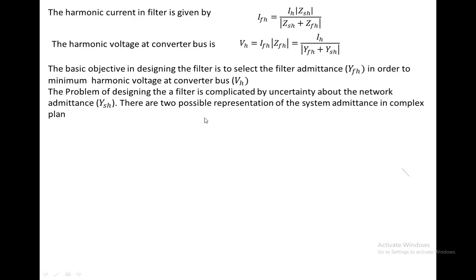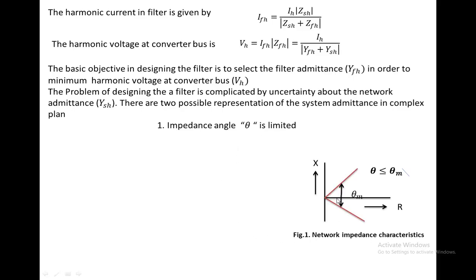There are two possible representations of system admittance in complex form. In the first method, the impedance angle theta is limited. On the x-axis we have resistance and on the y-axis we have reactance. Theta_M is the maximum impedance angle of the system admittance, representing the angle between the two impedance boundary lines. We select the system admittance such that it is less than the maximum admittance angle of the system.